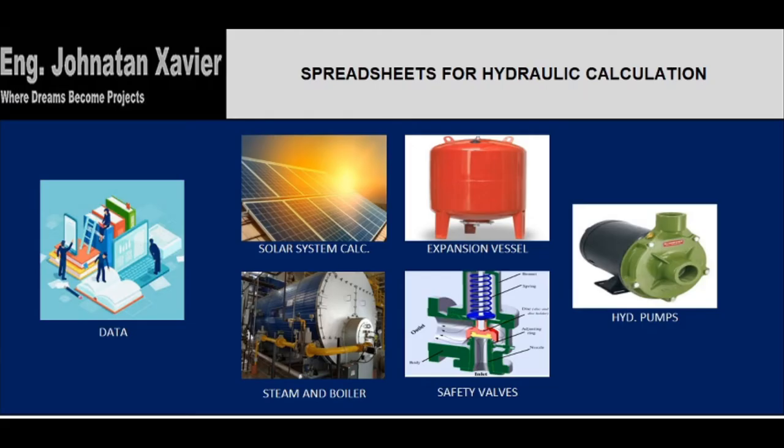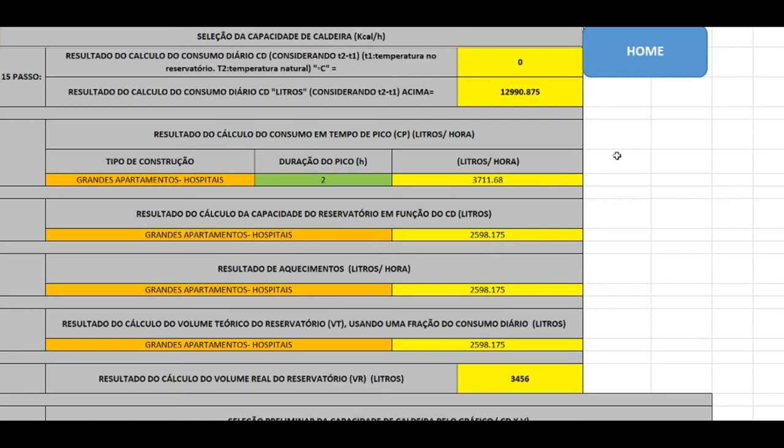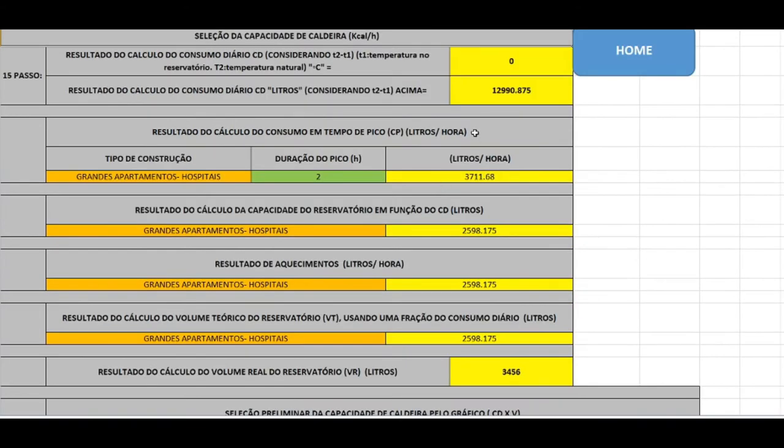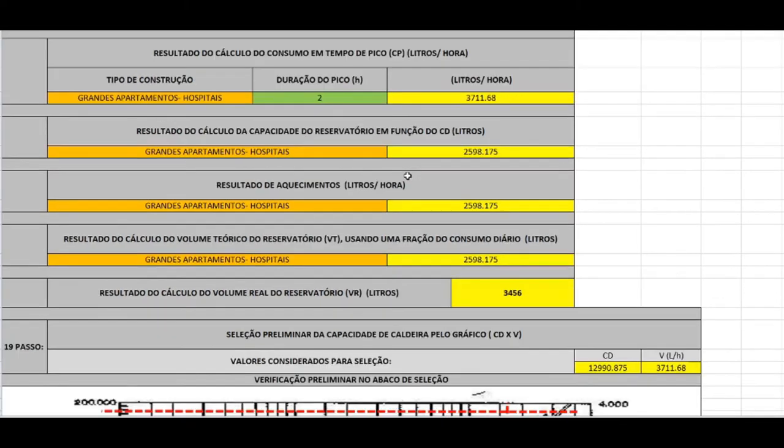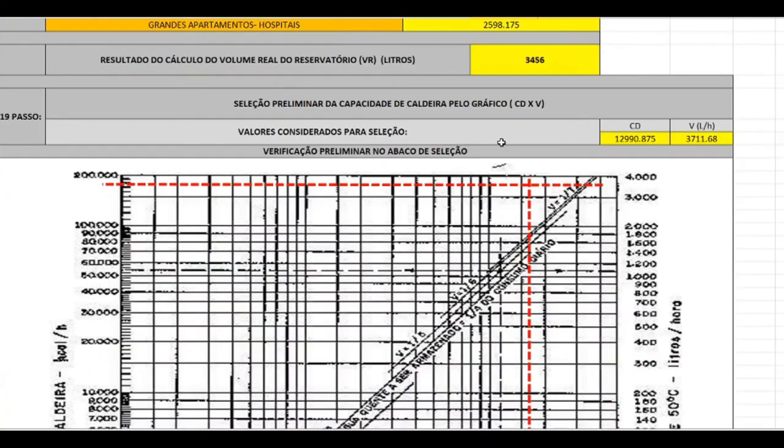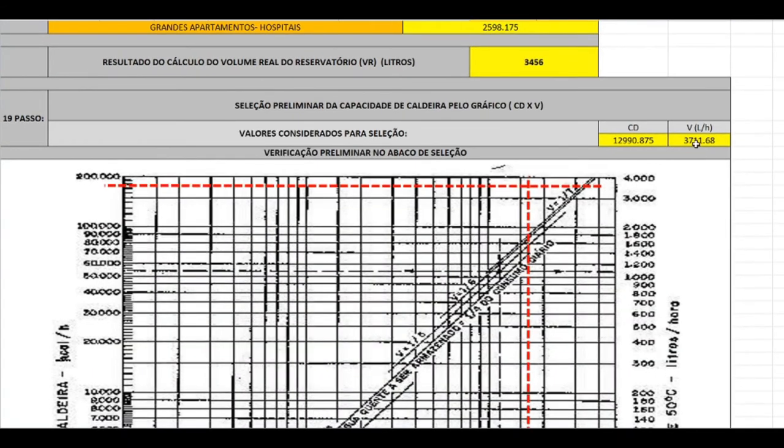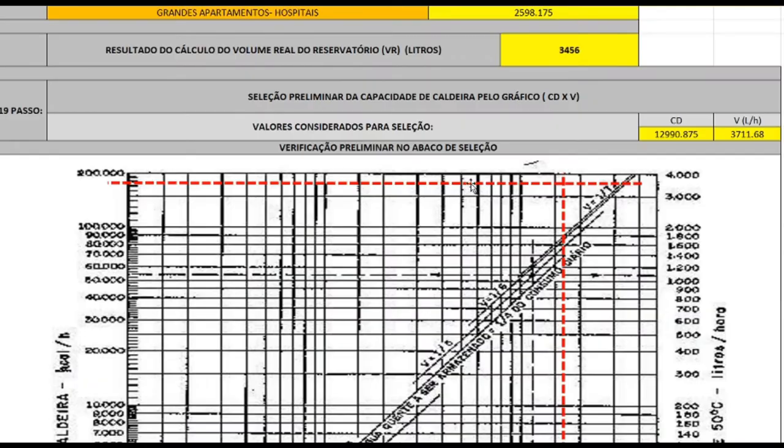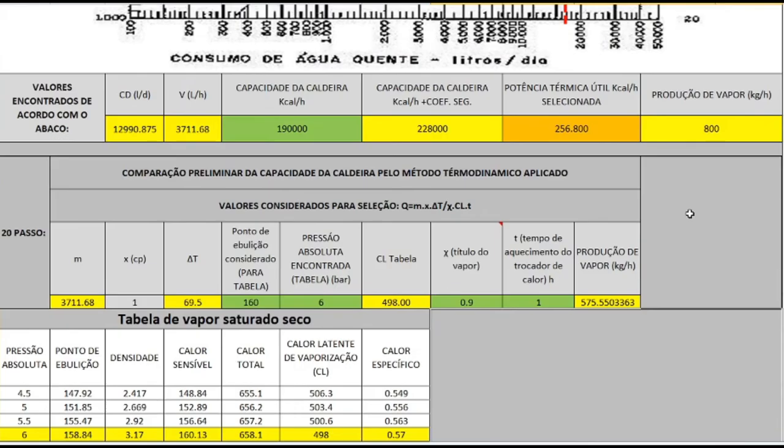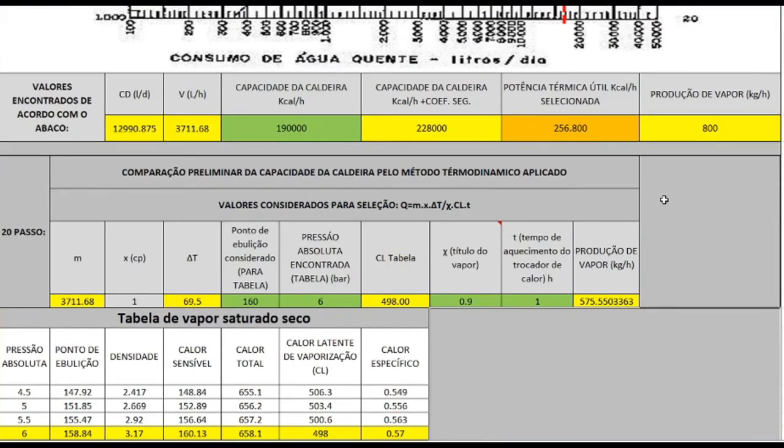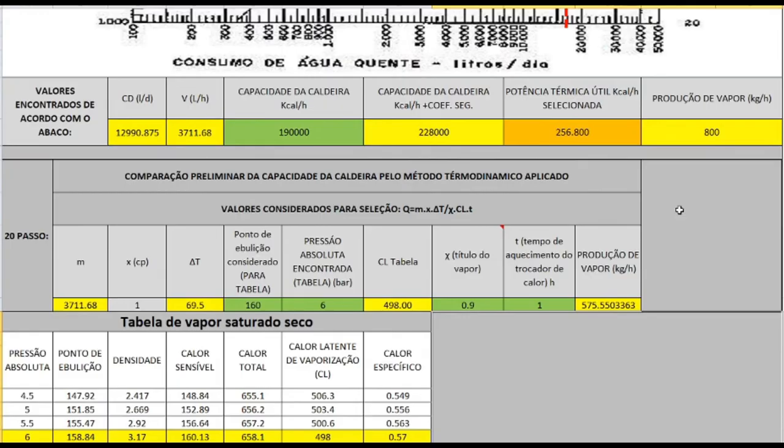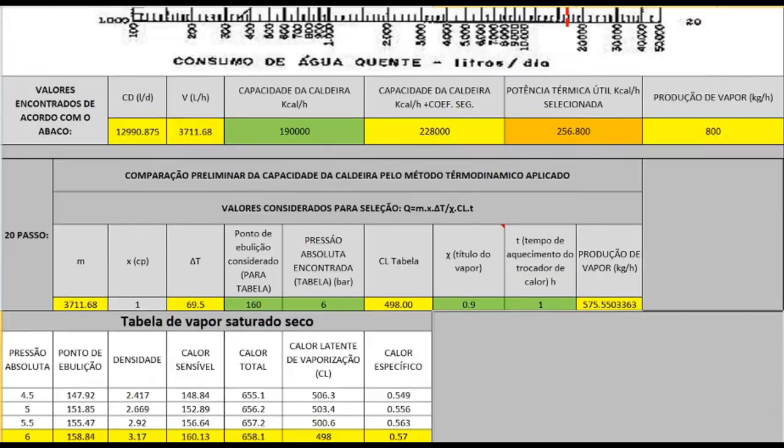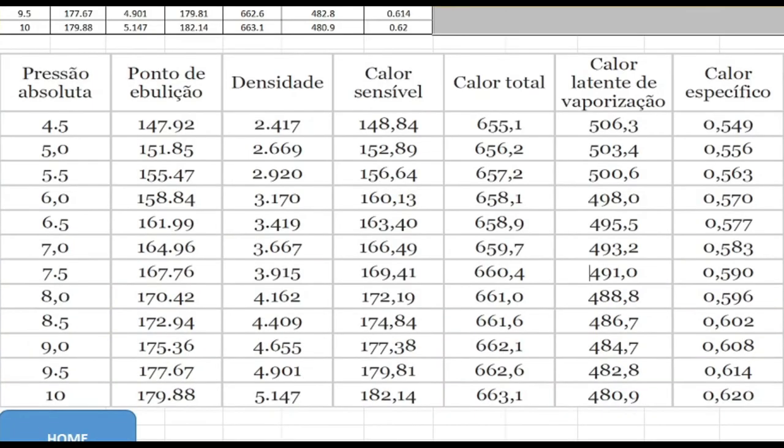The steam and boiler sizing spreadsheet was also prepared within the standards of this discipline, obtaining the results of the steam production required for each case. Obviously, the boiler manufacturers are consulted to obtain a commercial result. As we can see here, we have all information about hot water and the steam needed for this amount of water. As we can see, the table gives to us automatically all information needed for the selection of the boiler and all steam line.